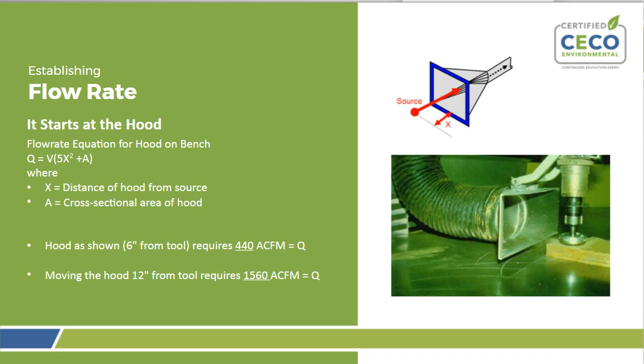And we can see in this photo, there's a flanged hood, flex duct with just a flange on the end. Again, this represents a hood that functions based on capture velocity. What we're noting here is the distance between the source and the hood. Just moving from 6 inches to 12 inches, the airflow required actually increases by 3.5 times, from 440 ACFM to 1,560 ACFM. So when you have a hood relying on capture velocity where there is some distance between the source and the hood, the placement of that hood is quite important. And we can see it here with a canopy type hood.